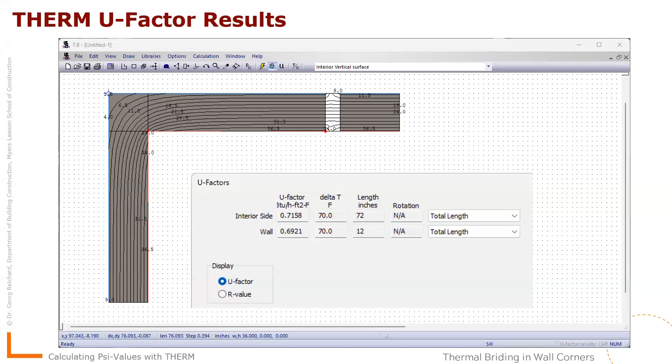So in our example, if we go back here, we will have to write then that our Psi value is, first of all, the total loss that exists. So the total loss is defined by 0.7158 as the conductance, the average conductance in the corner multiplied with the length that we have here. And we use, we set the tag for both of those legs and we can pick up the actual length. And you should check there that it's correct where you applied it and you can see it's 72 inches.